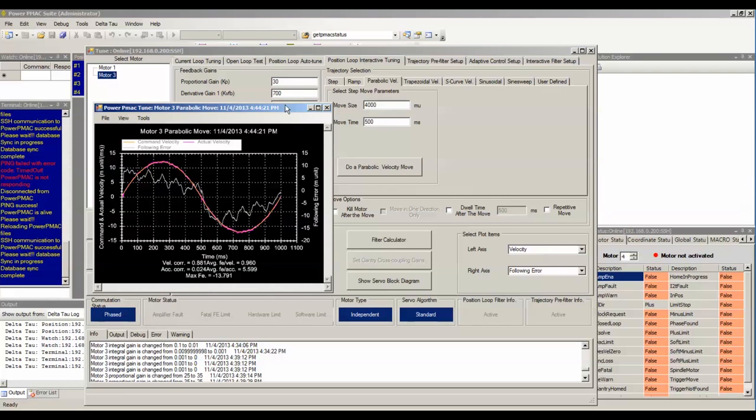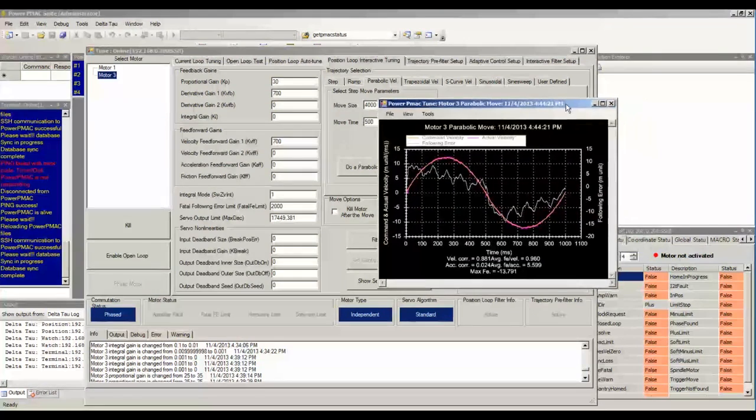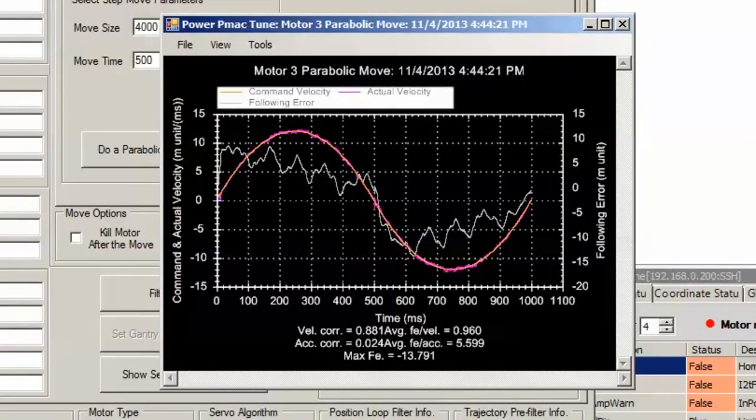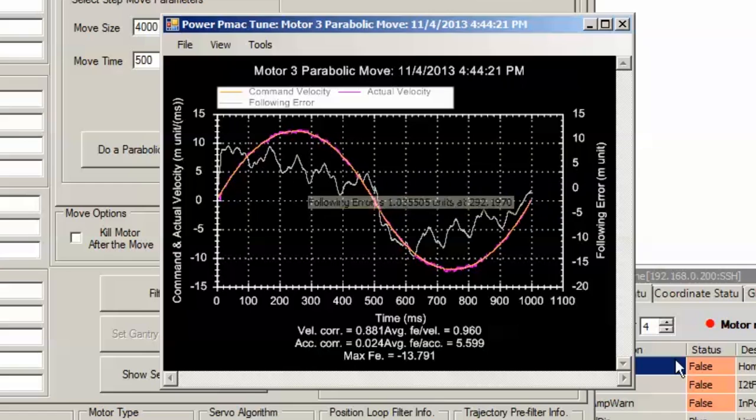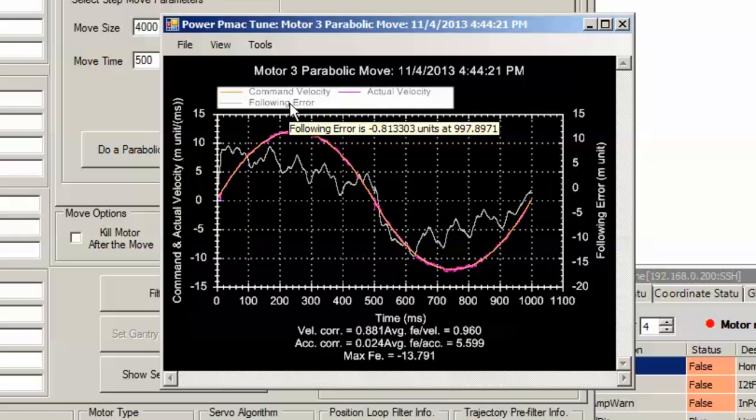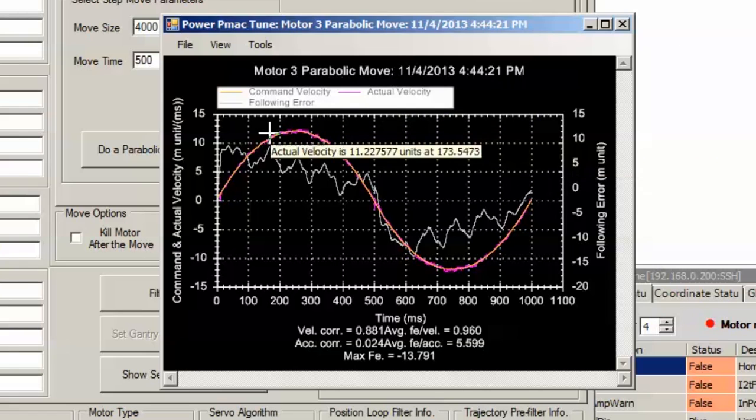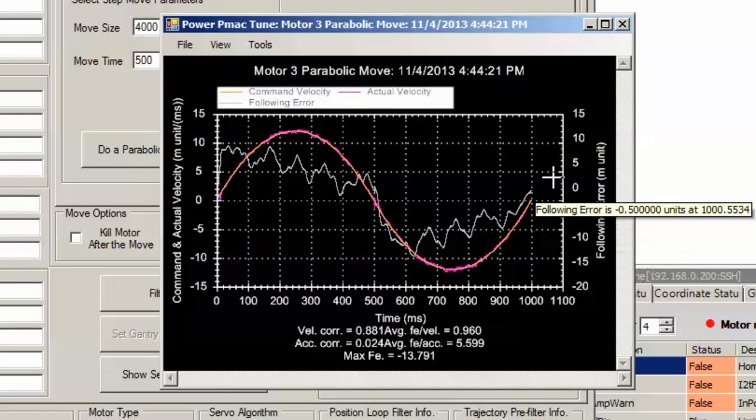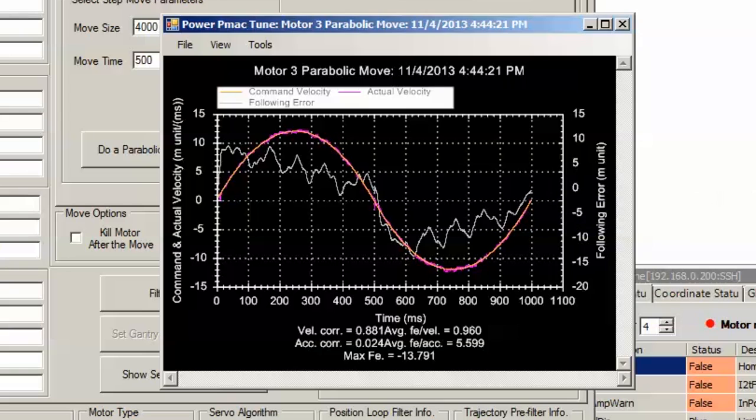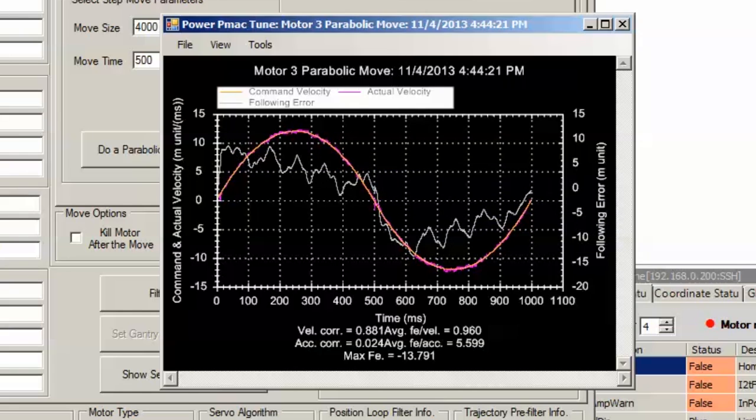We see in this particular case, we actually don't need to modify velocity feedforward. Its starting value of being set equal to derivative gain works just fine. We know this because there is no rounding in the left and right portions of the response. We are examining the following error and how it compares to the commanded velocity. We see that the following error dips down in a ramp like that on the left side, and then on the way back it slants up on a ramp. If we had seen any curvature in the left or right portions of the graph, we would know that we need to increase or decrease velocity feedforward. If you saw curvature that's the same shape as the commanded velocity, you know you need to increase velocity feedforward. If it is the inverse shape, you need to decrease velocity feedforward.